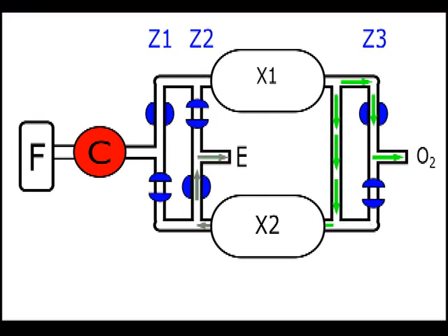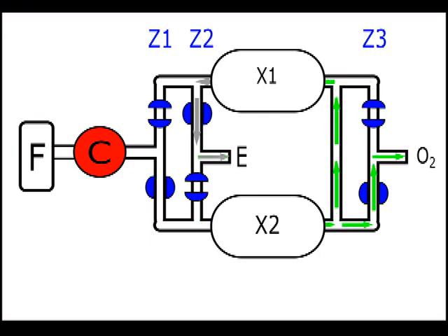This process goes on and on, providing oxygen for the patient for as long as the compressor, valves, and control circuits get electrical power to keep it working. Broadly speaking, this is the operating cycle of an oxygen concentrator.